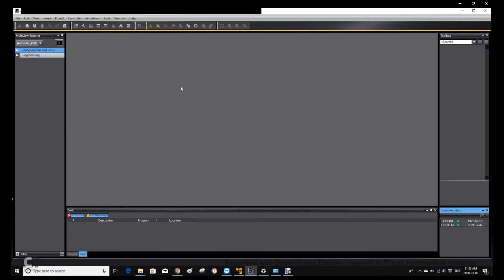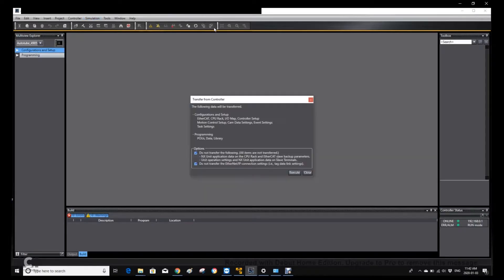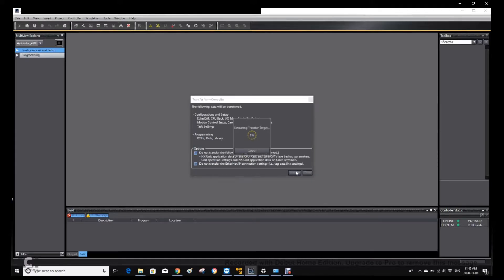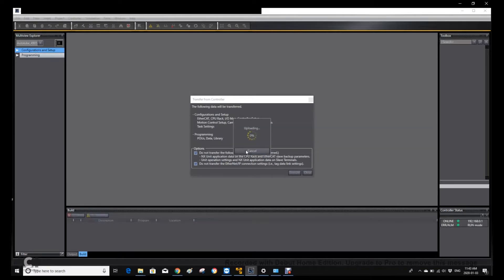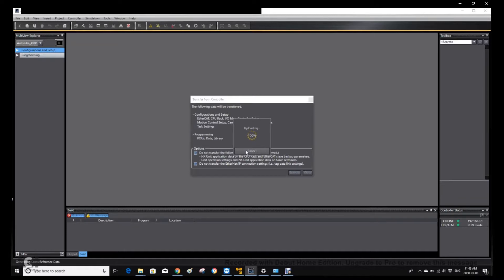So next, we will upload the program from this PLC. And with the current selection, we can see this checkbox. If it's checked with this, that means we just want to upload the program. We don't upload the hardware configuration. Because check means do not transfer.